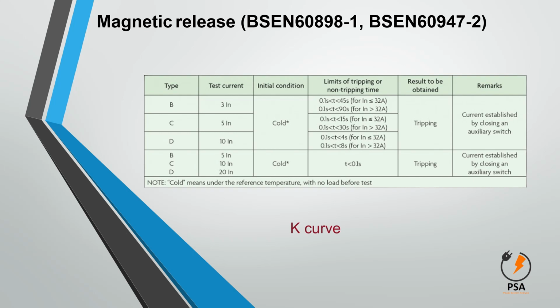K curve. In this, the CB trips when the current is between 8 to 12 times the full load current. Z curve. In this, the CB trips when the current is between 2 to 3 times the full load current. S curve. In this, the CB trips when the current is between 7 to 13 times the full load current.